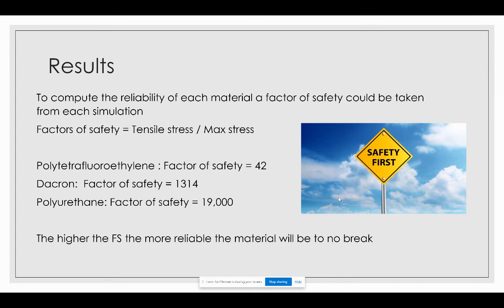To assess the reliability of each material, a factor of safety is taken from each simulation, calculated as tensile strength divided by maximum stress. For PTFE, the factor of safety is 42. For Dacron, it is 1,314. For polyurethane, the factor of safety is 19,000. A higher factor of safety means the material is more reliable and less likely to break. We want a higher factor of safety for materials placed in the human body, because failure can be catastrophic and life-threatening.